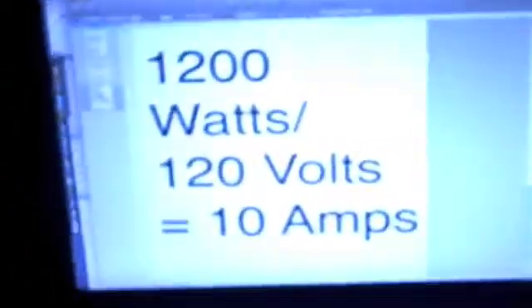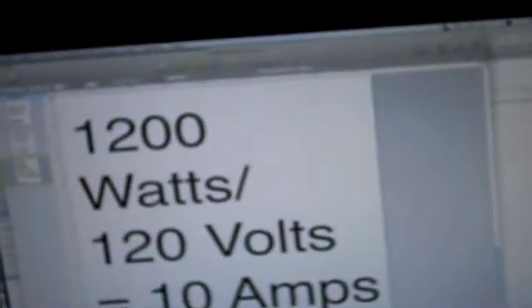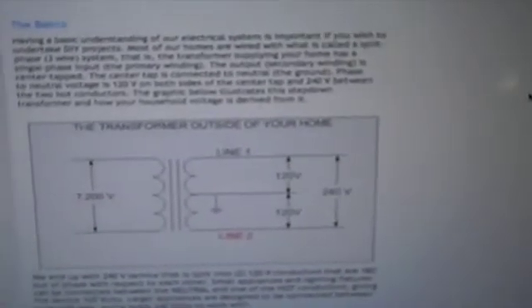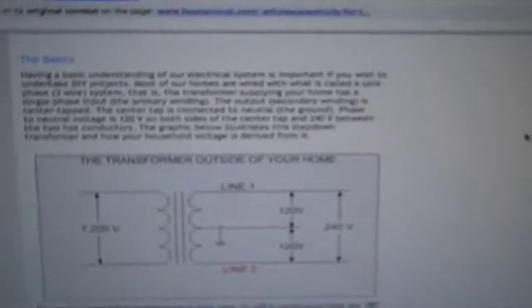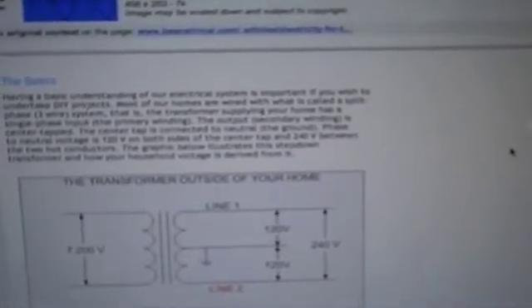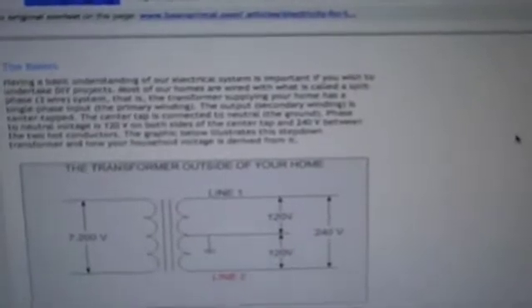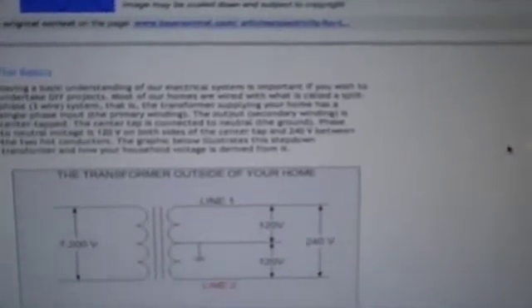We need to look at one other thing here to explain the way power works. Power comes into your house at about 7200 volts outside typically. When it comes in, it goes to a step-down transformer which takes it down to what's called split-phase or two-leg three-wire power. The middle wire is neutral, and then there's two powered legs, line one and line two, each at 120 volts. But if you combine the two of them together, you add a 240 volt level. So what's coming into your house or most businesses, including clubs, is 240 volts, but then it's divided so that what's coming out of the electrical outlets is 120 volts.